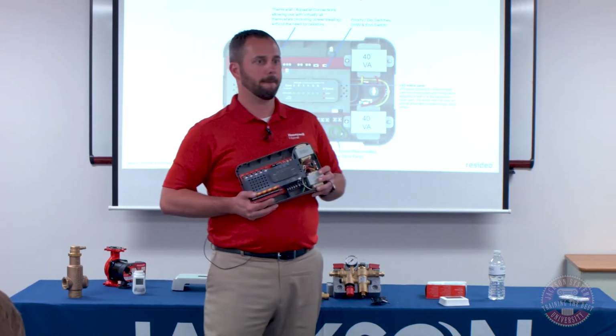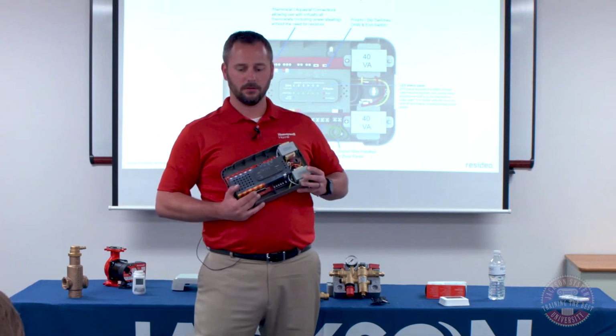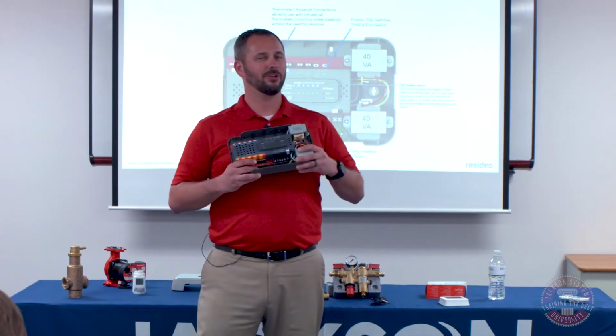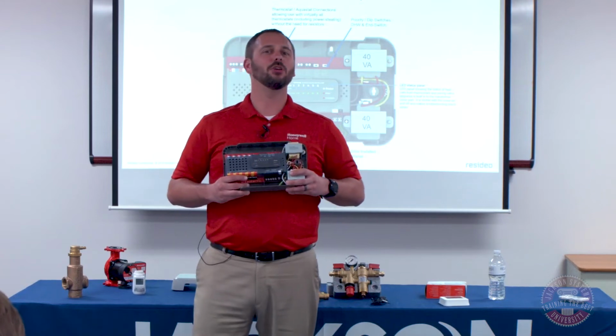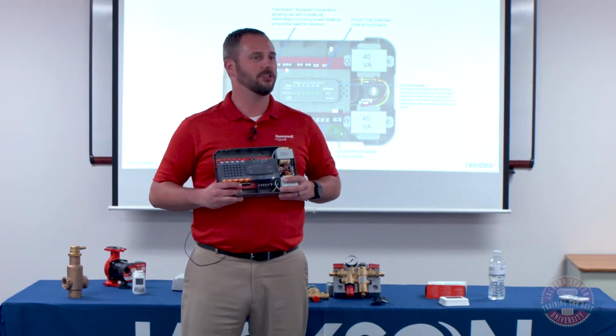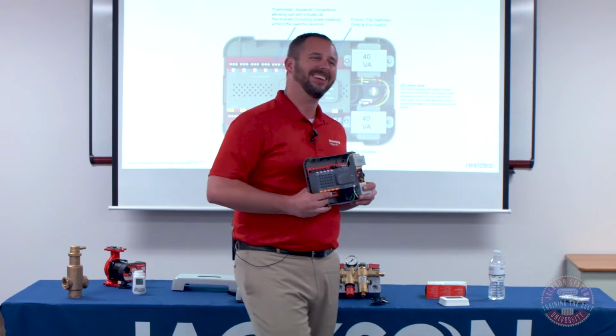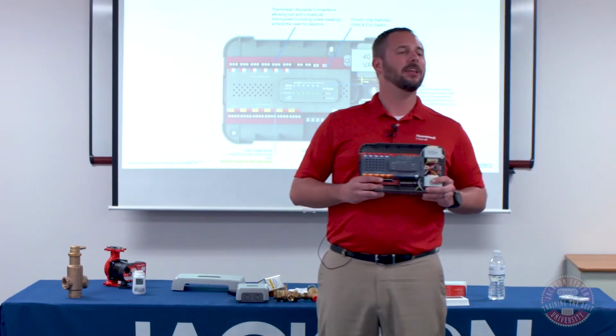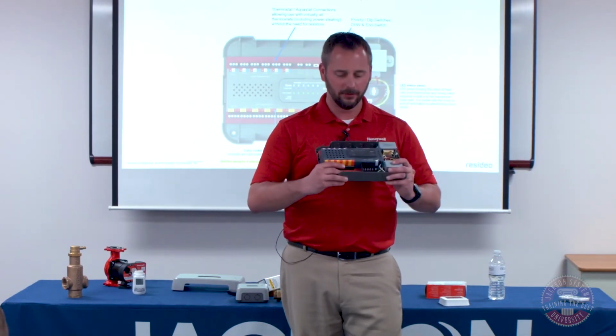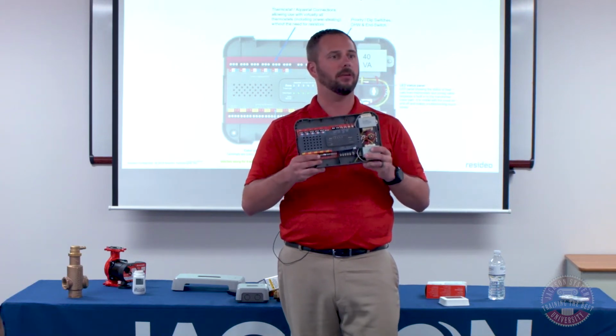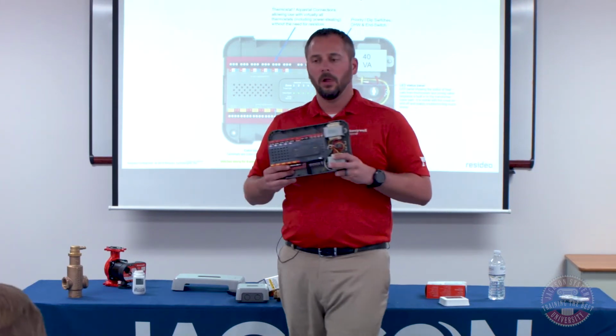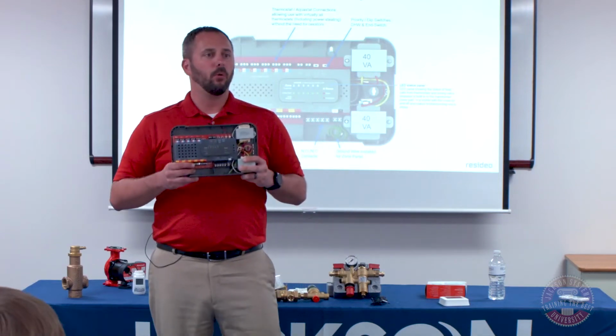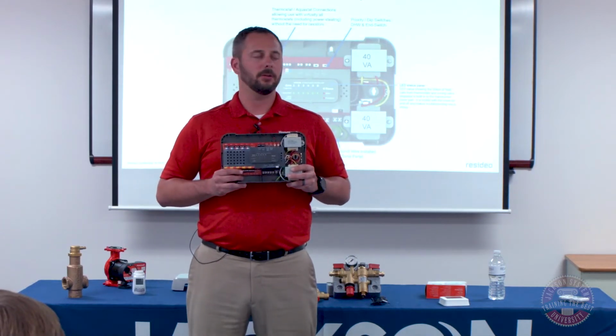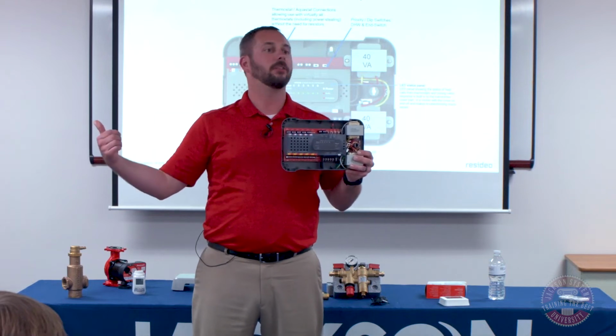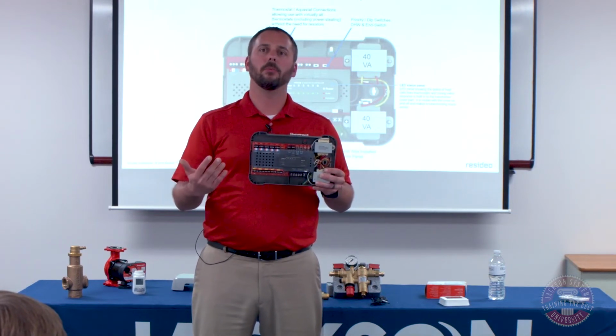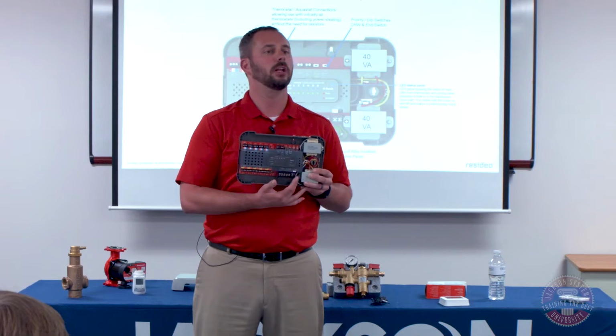From Constantino, and I think you're probably going to be answering this in a minute, but he asked, how many zones can you control? Good question. So I haven't even used my favorite hydronic answer to questions yet. It depends. So what you're looking at with this is how many zones can you operate with this. So in this example, I am holding in my hands a 5-zone control. Depending on the boiler you're using, you can ultimately indefinitely expand these things. So it depends on the boiler you're using, and it depends on the relays that you need to operate.